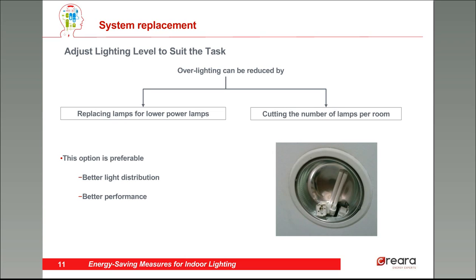Overlighting can be reduced by replacing lamps with lower power lamps, or cutting the number of lamps per room. The first option — reducing the power of lamps — is preferable, since it serves better for light distribution and luminaire performance. But the most common is the second option: cutting the number of lamps per room. This is not ideal — we can see a picture of a luminaire prepared for two lamps but with only one lamp. This is very common because with this option you don't need an investment and instantly you reduce consumption by 50%.